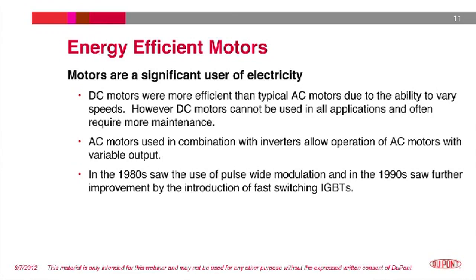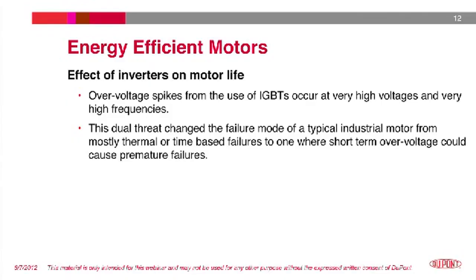In the 90s, further efficiency improvements were made to the inverters by the introduction of fast switching IGBTs, insulated gate bipolar transistors. Initial enthusiasm for this new type of energy efficient motor was, however, met with an increase of motor failures versus AC motors operated with conventional motor controls. Investigation into the cause of failures identified overvoltage spikes caused by the use of the IGBTs in the inverter systems. These spikes were both at very high voltages versus the system voltage of the equipment and at very high frequencies. This dual threat changed the typical motor failure from a purely thermal failure to one caused by a short-term overvoltage.